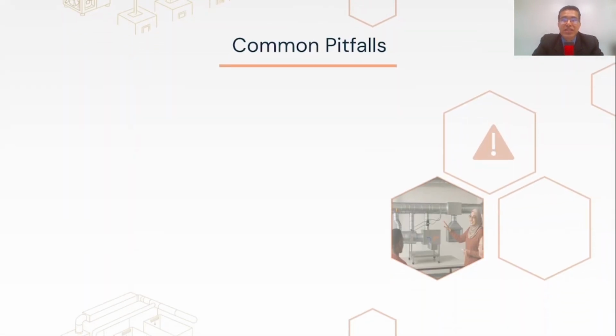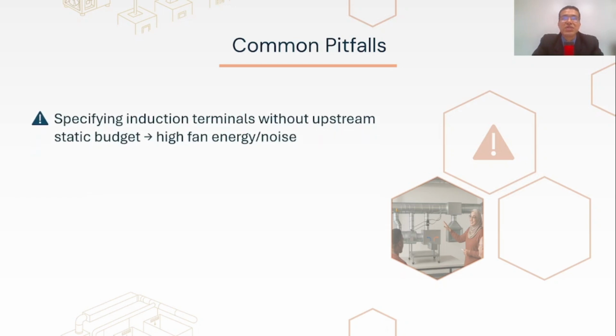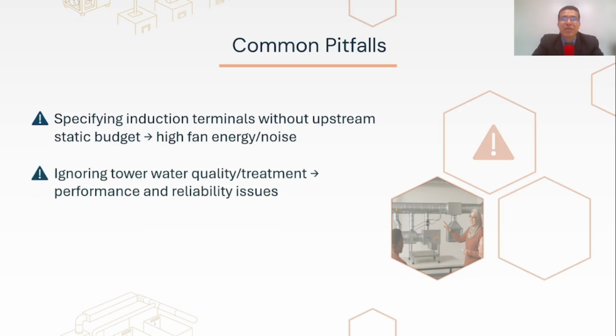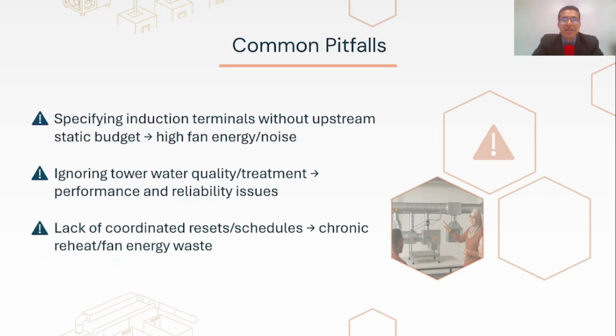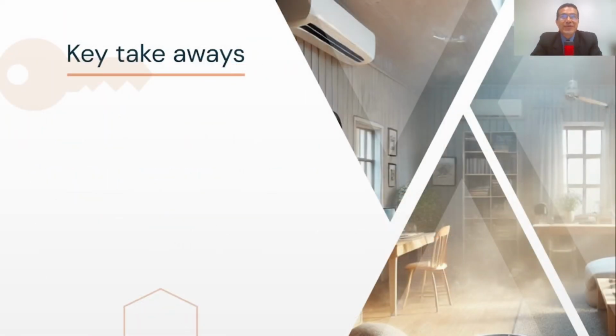Now we'll turn our attention to the potential pitfalls that can arise in the design and operation of central and packaged systems. Terminal selections impact central fan energy. Induction devices require explicit static allowance. Cooling towers demand planning for makeup water and treatment to sustain heat rejection performance. Without supervisory resets and scheduling, systems may consume unnecessary reheat and fan power at part load. Let's finish this lesson with some key takeaways.